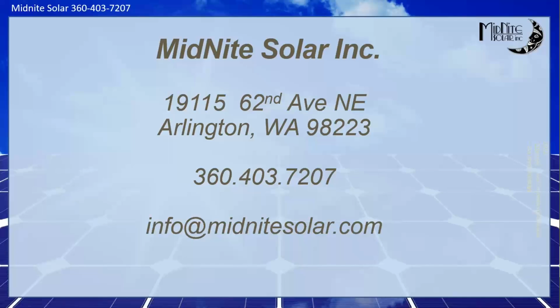I do have one question. In an always off-grid situation, can we assist loads between a Rosie and a generator? Say Rosie is feeding, but not enough. Can the generator kick in and help? Yes, that can go both ways. So Rosie has what we call load transfer. So you could tell it, hey, if the load exceeds a certain amount, pull in something on the input, be it generator or grid, and run the load.